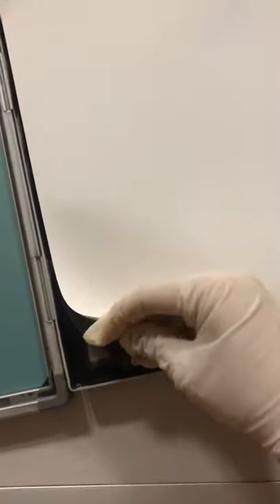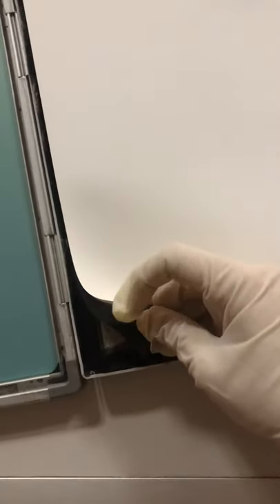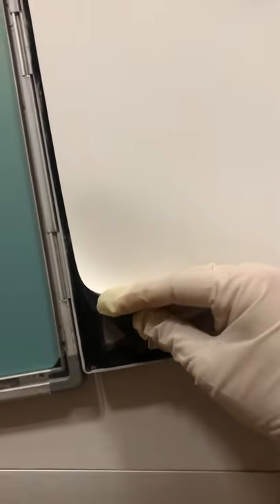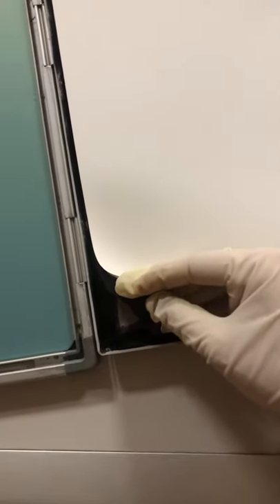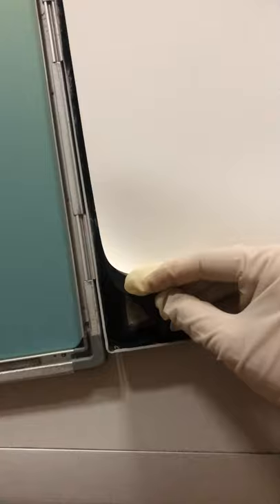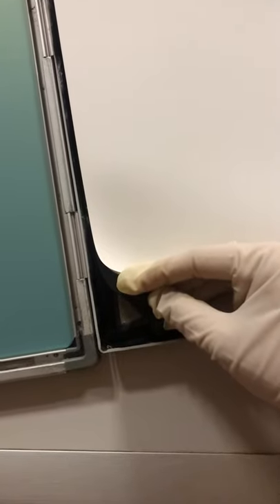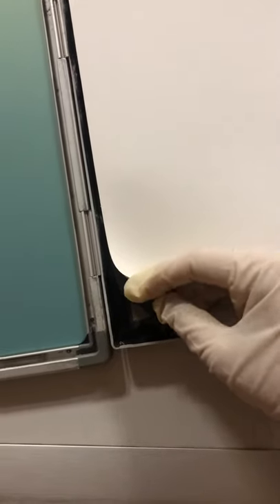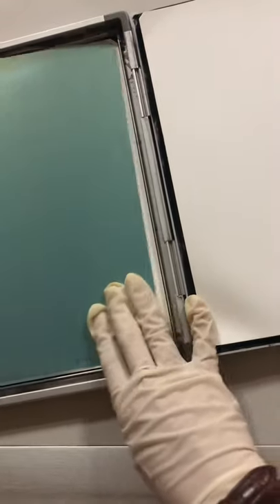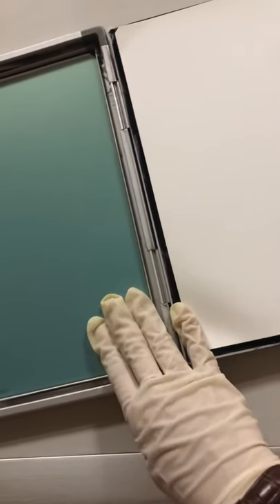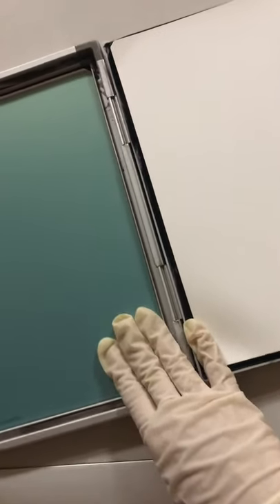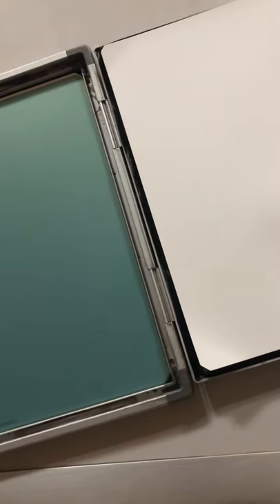Also called a foam pressure pad, the function of the felt pad is to maintain the screen, the film, and its fellow screen in uniform contact. Proper film and screen contact is necessary to achieve good image detail.